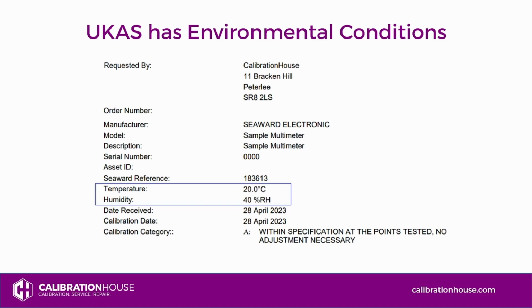A UKAS certificate will also have the environmental conditions listed. So you can see here, temperature and humidity were within the tolerances that are acceptable for a UKAS calibration. A traceable certificate normally doesn't have this information.